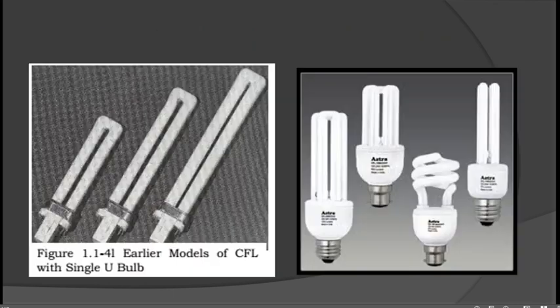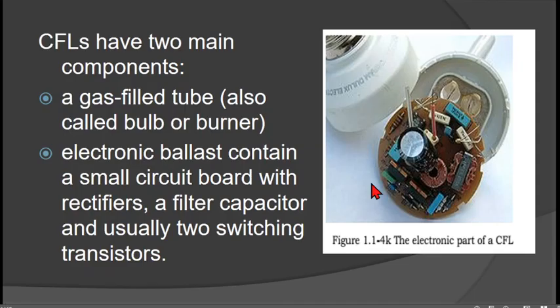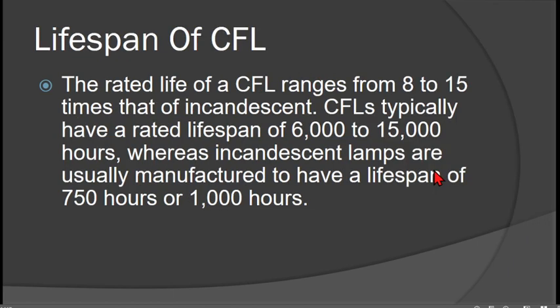The CFL, or Compact Fluorescent Lamp, also has an electronic ballast and comes in different sizes. Its components are a gas-filled tube and an electronic ballast. The lifespan of a CFL is 8 to 15 times that of an incandescent lamp, at approximately 6,000 to 15,000 hours, compared to 750 to 1,000 hours for an incandescent lamp.